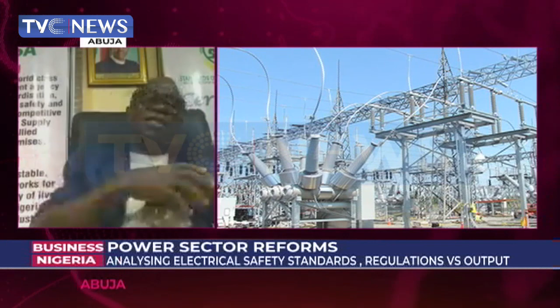That's one. Two, the 33 kV lines are supposed to carry power just between two points, from transmission to injection substation. It has what we call a capacity of what they can carry, the evacuation or wheeling capacity. In most cases, for a 150 mm conductor, which is mostly used, the total capacity is 25 megawatt. But when you now calculate the total load on this line, sometimes we have a case where we have 76 megawatt load on a 25 megawatt capacity.